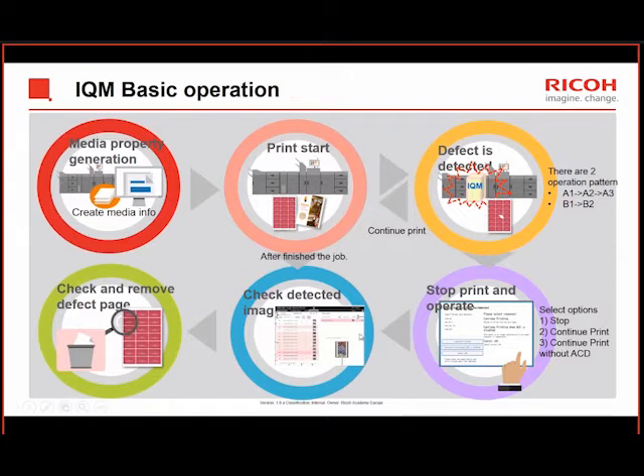Over here, you see the user interface, and on the user interface, you get a thumbnail image with an example with the error code, with the error displayed. So if it's a white line on the thumbnail image, you can see that white line. It's just unfortunate that you get this screen that just gives you a code, and I think if you don't explain that to your customers, it will cause service calls, because all they see on here is an error code. They need to then look at the user interface to find out what's actually happened with the image. So it's something that you need to train your customers to do.